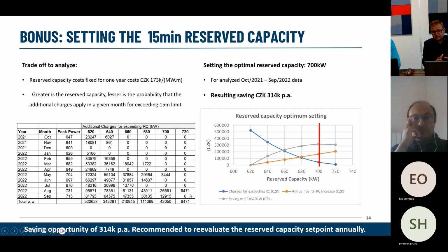But okay, you can say, I'm going to increase the reserve power, so I never have an excess. But you have to pay for that reserved power capacity. And as in every other scenario, there is that rule of diminishing returns. If you invest too much, it stops paying back. So you can see the charges for exceeding are the blue curve. The saving versus the reserve power, that's the gray curve, because we compared with the annual fee for the reserved capacity, which is the orange. So somewhere at 700 kilowatts of reserve capacity, that's the optimum for the company. And by doing so, they will save 300,000 every year.